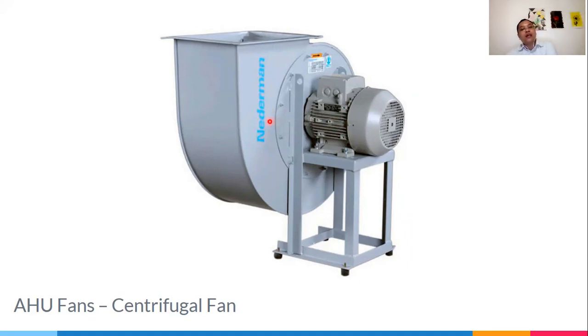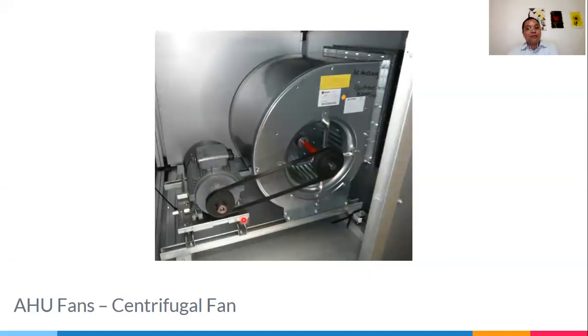These two are reconciled by using a variable frequency drive, VFD, or variable speed drive, VSD. I'll use the term VSD. By using VSD on the electrical connection to the motor, you can manipulate the frequency, the rotational speed of your motor, and in turn, directly connected to your fan. So you save on belt and pulley, you save on equipment, and you save on maintenance.